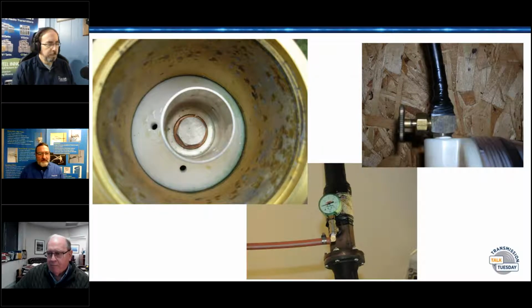One more thing about what to do if there is moisture: using dry air isn't going to get out standing water. You can draw a vacuum, which will vaporize the water, turn it into water vapor, and pull the moisture down through the vacuum pump. But be sure to disconnect the vacuum before you turn it off, because it'll suck the oil back up into the line. We've actually seen that happen, and the connection was all contaminated with oil from the vacuum pump.